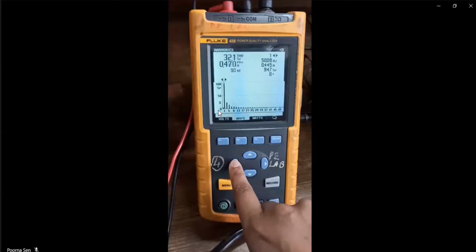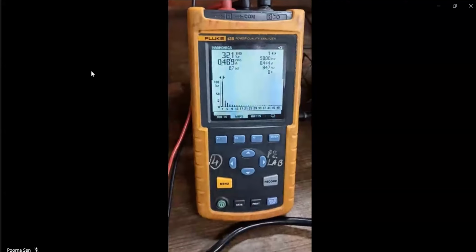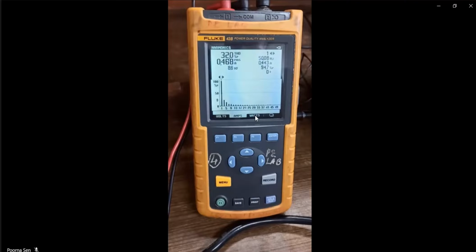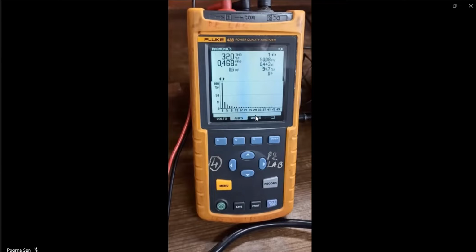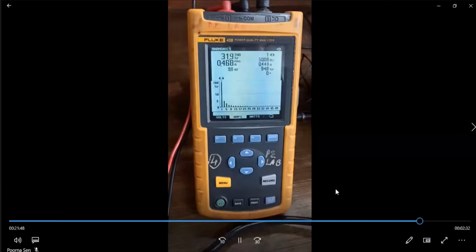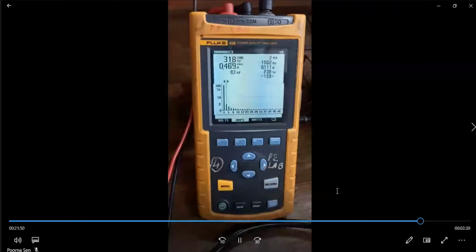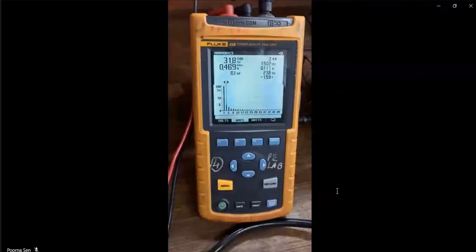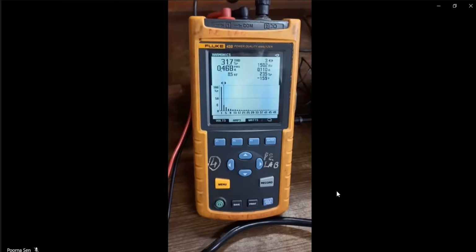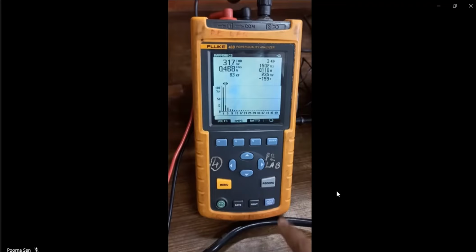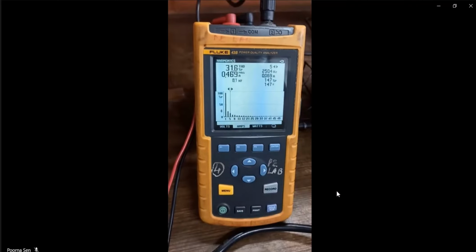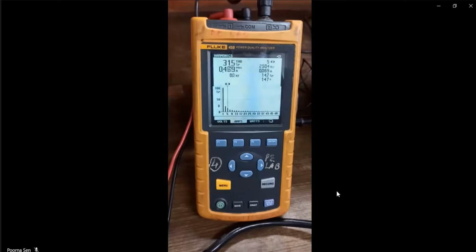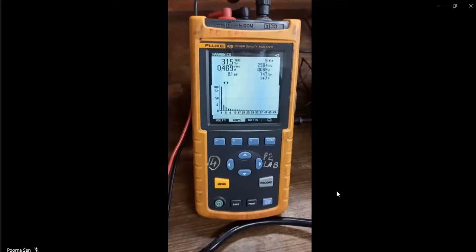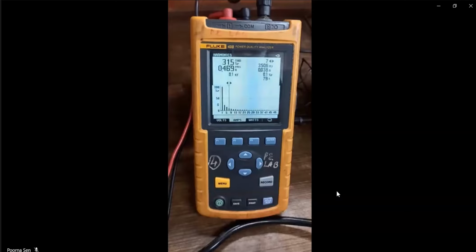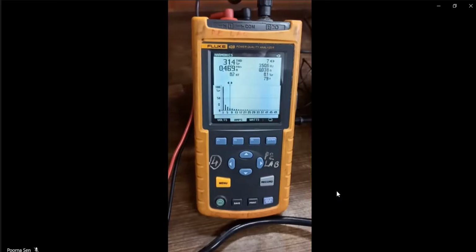THD is 32.1%. First harmonic 443 milliampere. Third harmonic 110 milliampere. Fifth harmonic 0.069 ampere. Seventh harmonic 0.037 ampere.